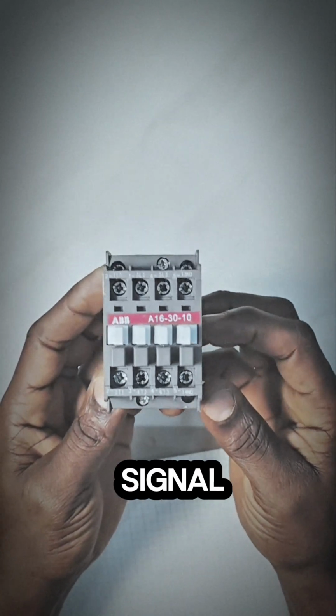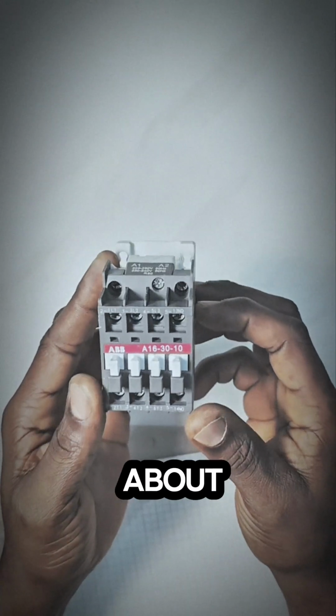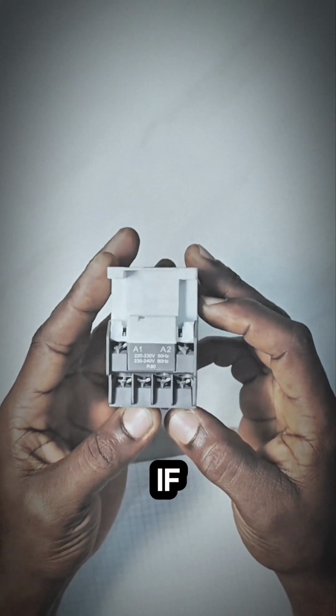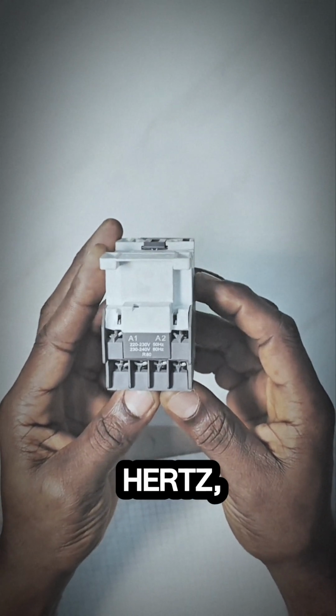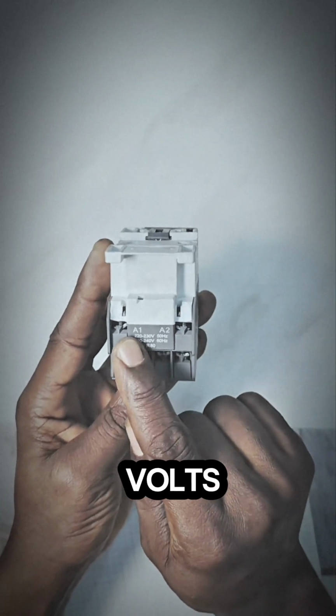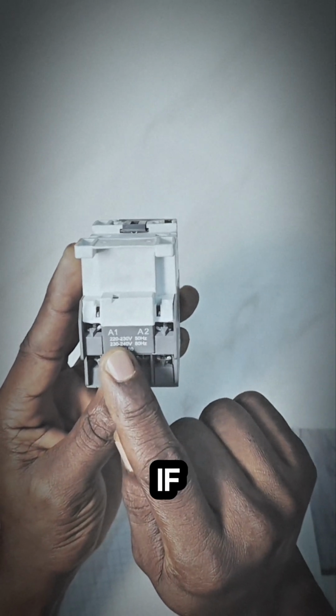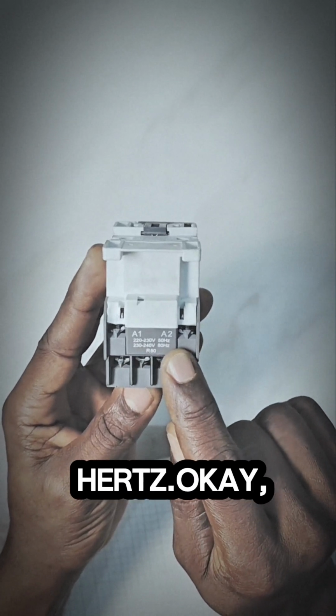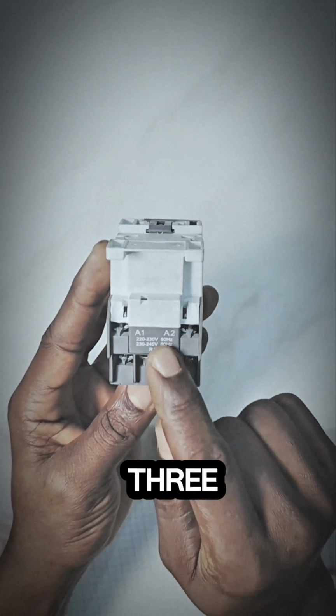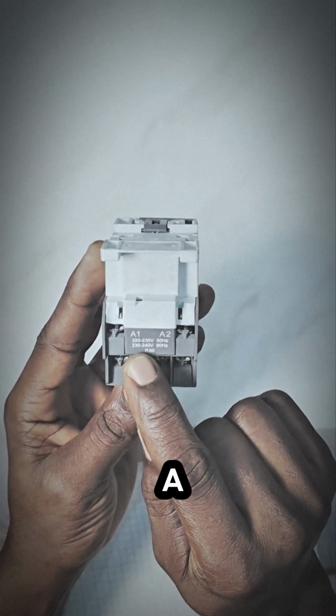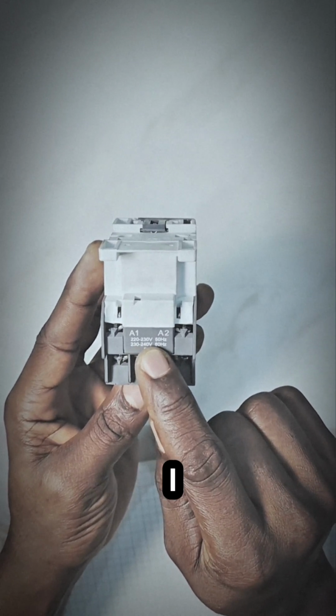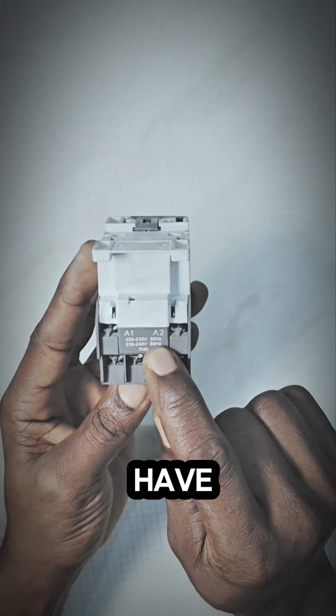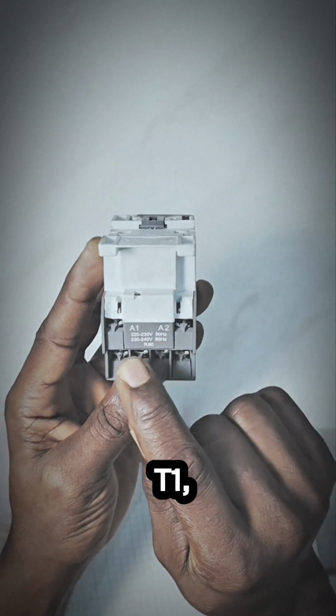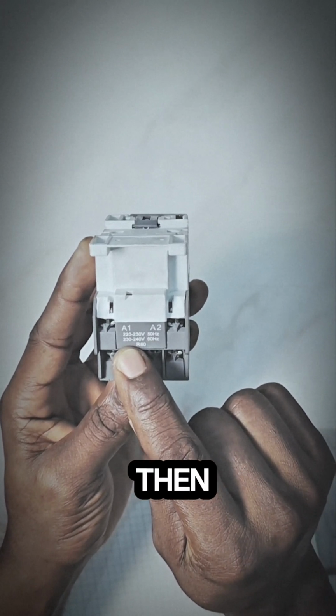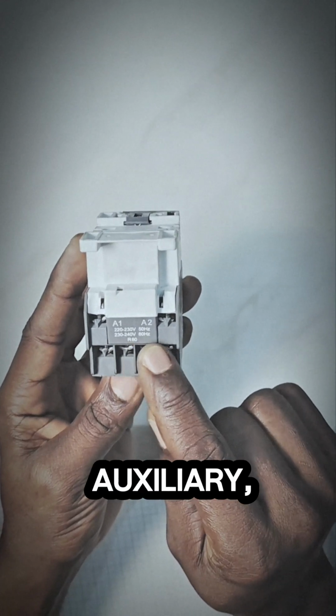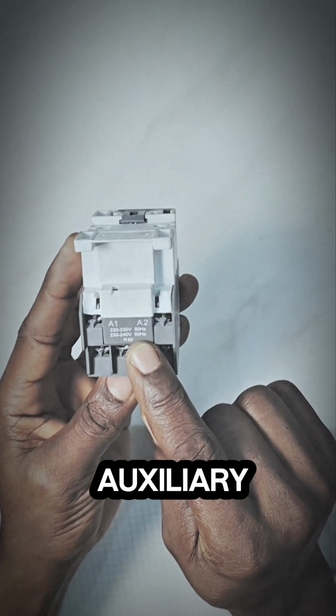The signal required to operate this one is about 220 to 230 volts if you are operating on 50 hertz, and about 230 to 240 volts if you are operating at 60 hertz. This is used to power three-phase equipment because it is a 3-pole contactor. What I mean is that we have L1, L2, L3, and T1, T2, T3. And then this other one here is the auxiliary, which is the normally open auxiliary terminals.